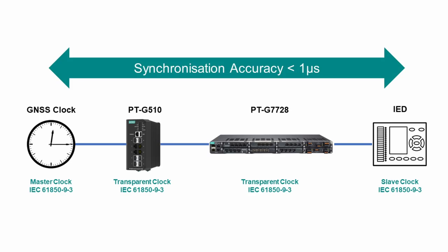To sum up, we've successfully set up PTP time synchronization in our small network using IEC 61850-9-3 profile, and this provides less than one microsecond accuracy that is needed for process bus applications.